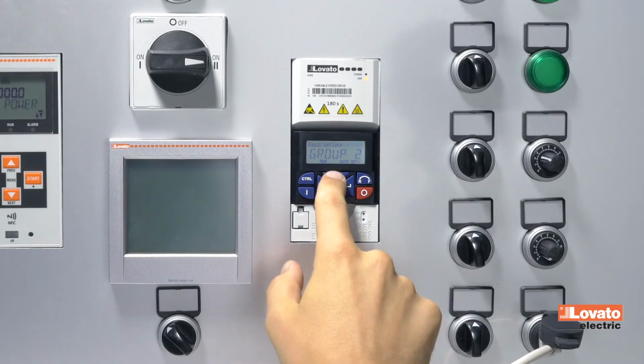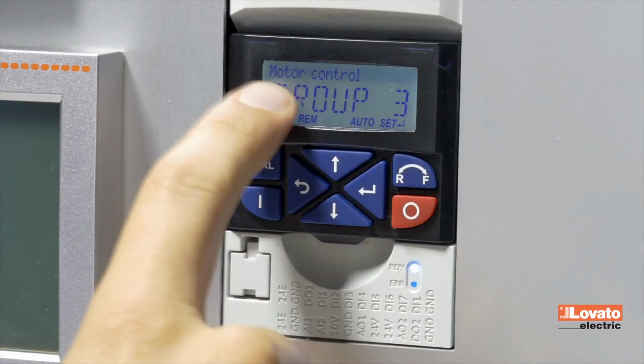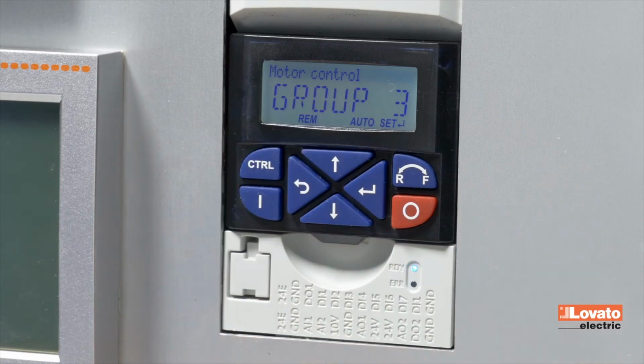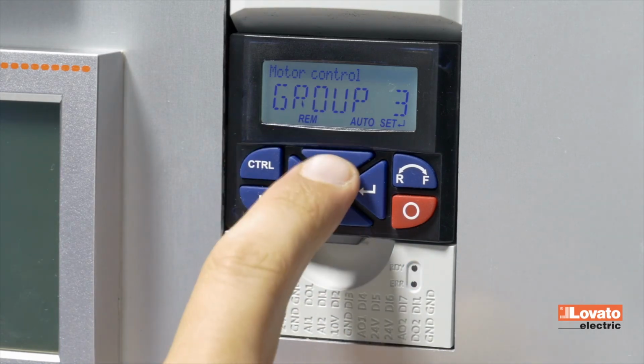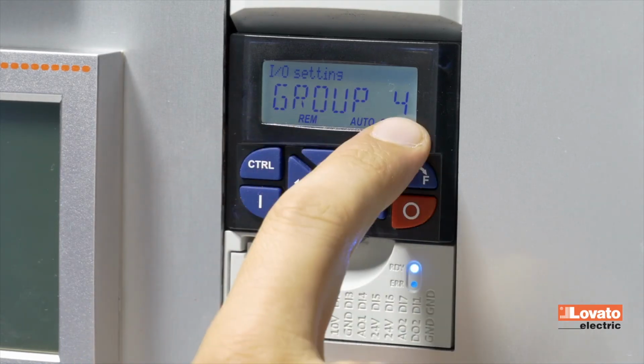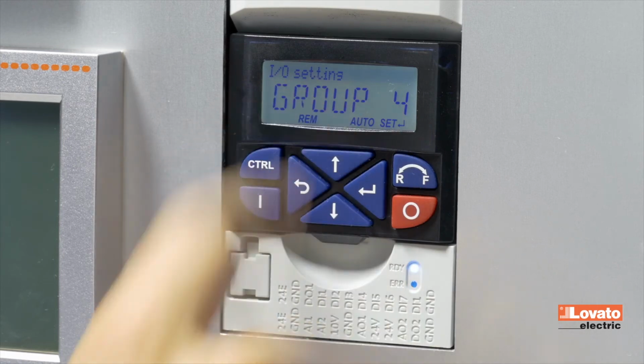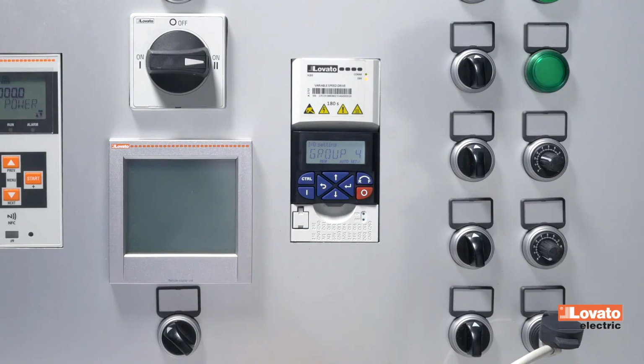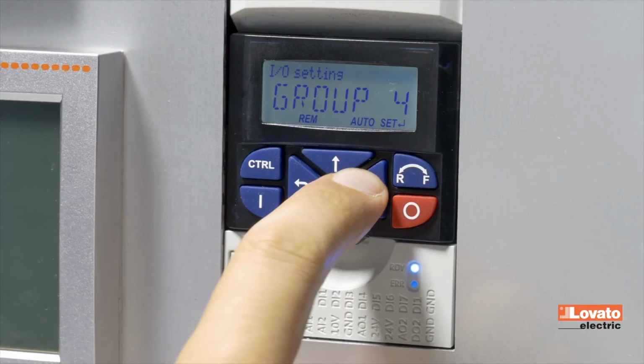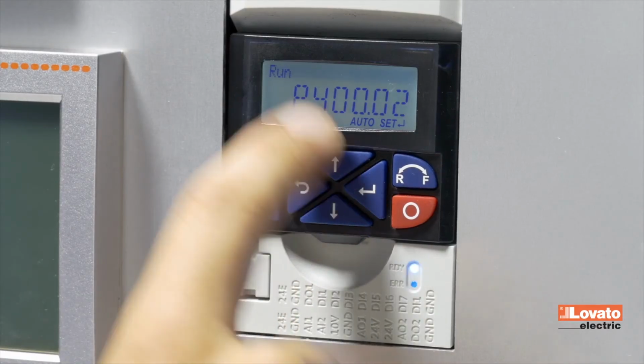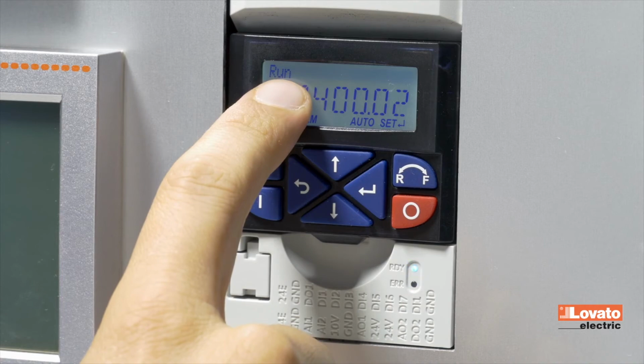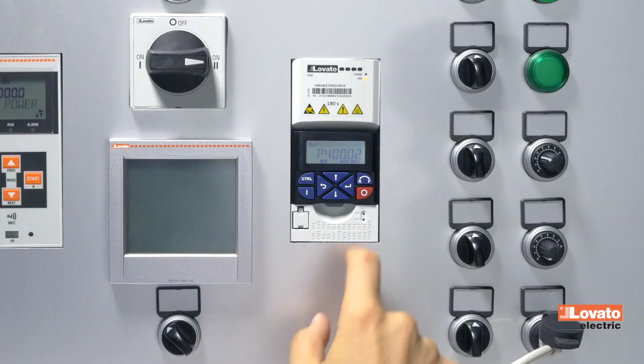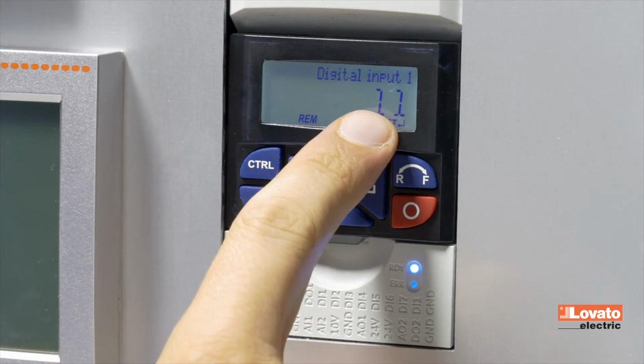Group 3 is used to set motor parameters, selecting the motor control mode and its rating plate data. Group 4 is for programming the functions of the inputs, both digital and analog, and of the outputs on board the drive. For example, the Run function is assigned by default to DI1, as shown here.